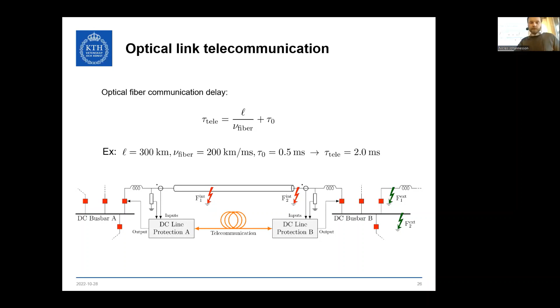The first protection that comes to mind is always the differential protection. It's a saying in the protection business that if you can, you should always use a differential protection. You basically calculate the sum of the currents, which should equal 0 unless there's an internal fault. The problem is that when you apply this for transmission lines, the traveling waves will generally not be equal during transients, which I've illustrated here in this example. That makes them a little bit sensitive. To overcome this, existing HVDC protection systems are slow, hundreds of milliseconds, which is way too long for multi-terminal protection.